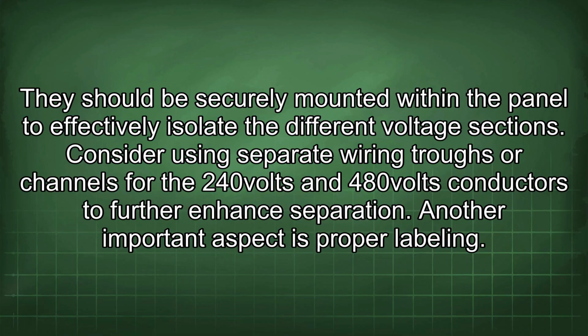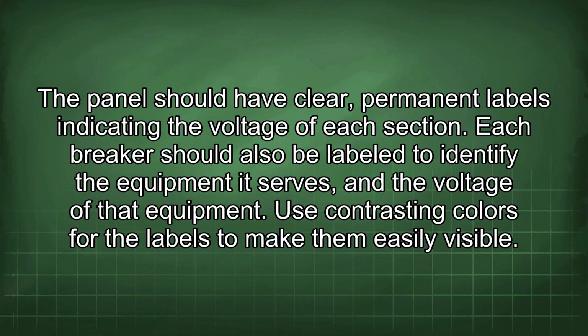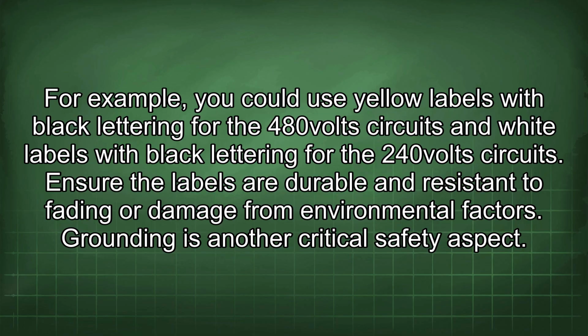Another important aspect is proper labeling. The panel should have clear, permanent labels indicating the voltage of each section. Each breaker should also be labeled to identify the equipment it serves and the voltage of that equipment. Use contrasting colors for the labels to make them easily visible. For example, you could use yellow labels with black lettering for the 480 volt circuits and white labels with black lettering for the 240 volt circuits. Ensure the labels are durable and resistant to fading or damage from environmental factors.